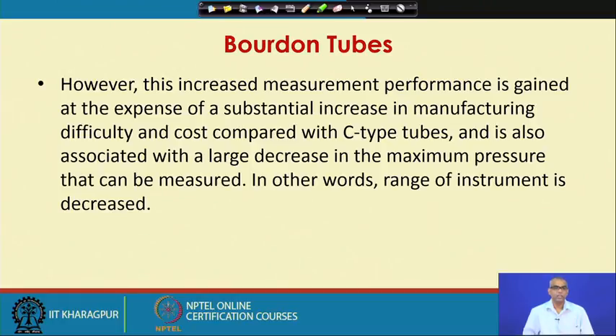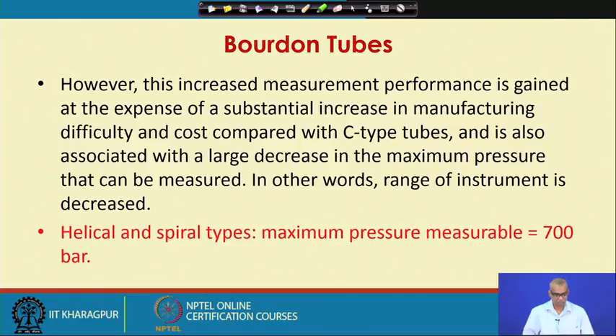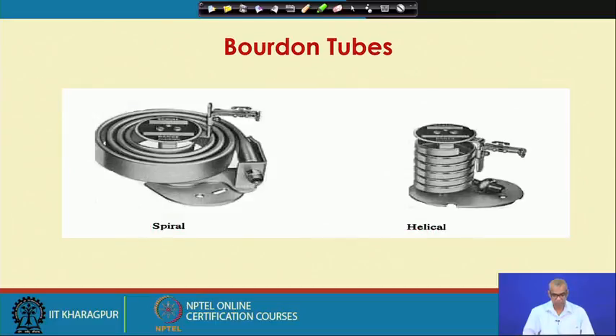So, you can increase the sensitivity of the instrument by increasing the length of the Bourdon tube, giving it a spiral or helical shape, but this comes with an increased cost and also the range of the instrument decreases. Helical and spiral types maximum pressure measurable is 700 bar. This is an indicative range. These are some photographs of spiral type Bourdon tube and helical type Bourdon tube.